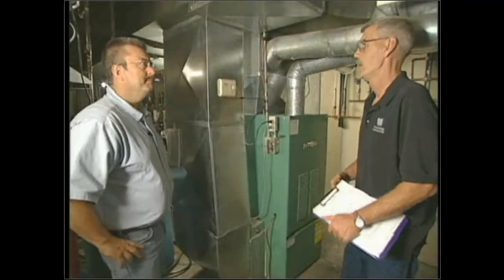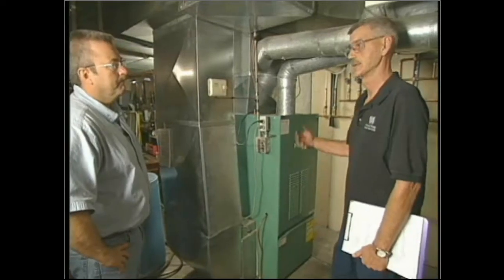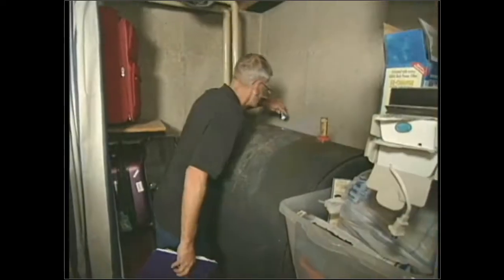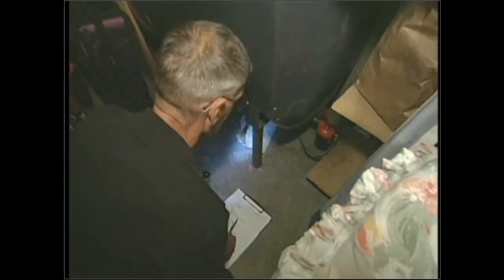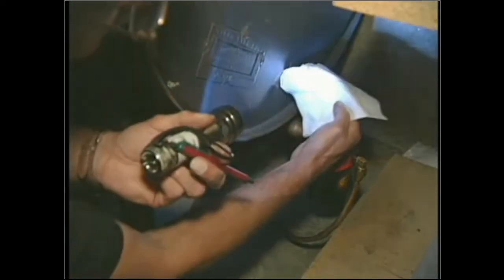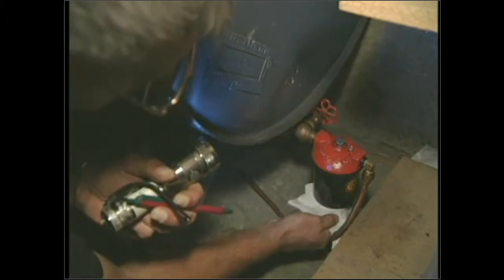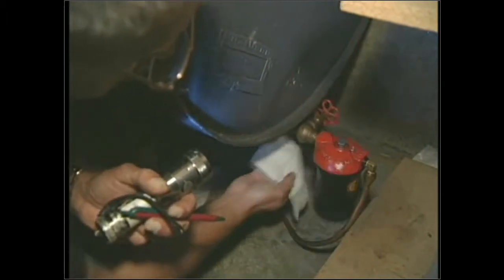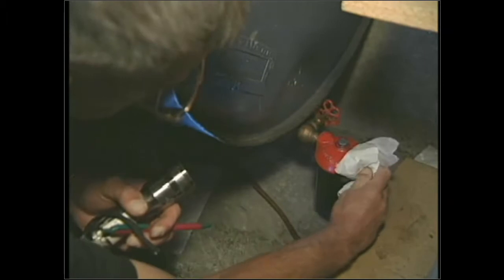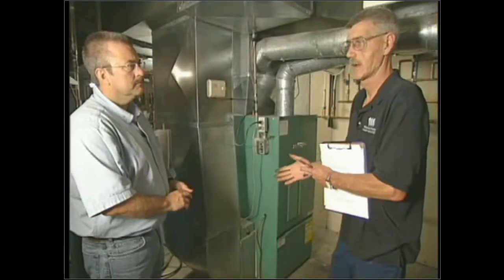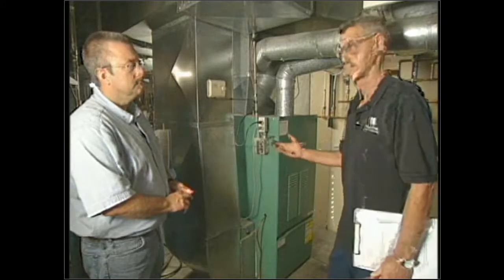Okay, so you complete your conversation and communication with the homeowner. It's time for the visual inspection. How do you begin that? Well, the first thing I like to do is check the fuel lines, just like we do with all the other systems. With an oil system, we can't check with a tester, so we have to do it visually. So I go to the tank, I take a piece of paper towel or a white napkin, and I will check the valve, I'll check the bottom of the canister, I'll check the sides of the canister where the O-ring is, I'll check the union. What I'm looking for when I pull it back is a little bit of reddish or yellow tinge to the paper, and that means that there's a potential for an oil leak.